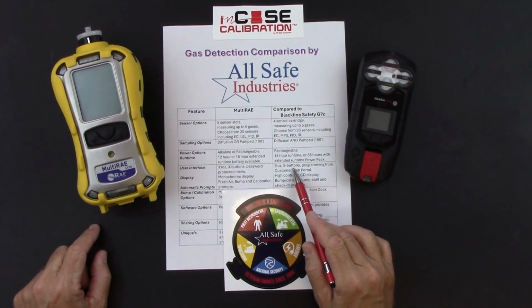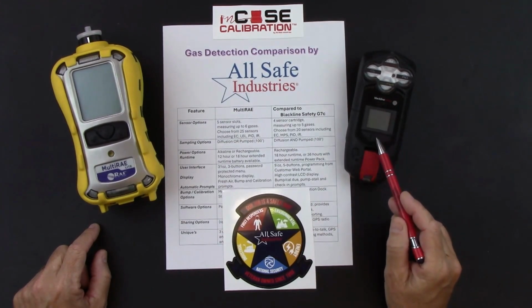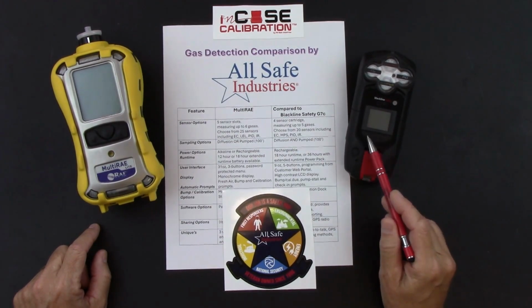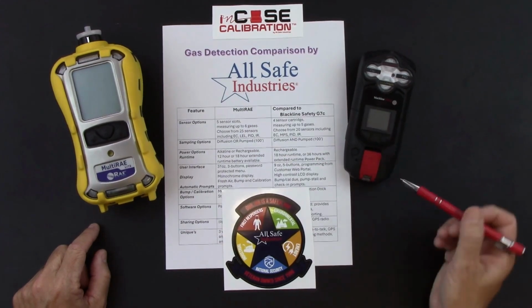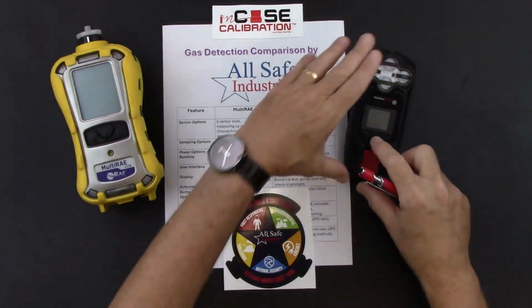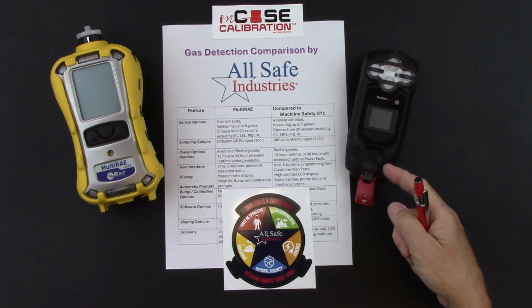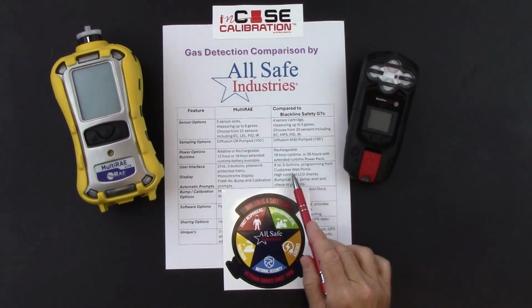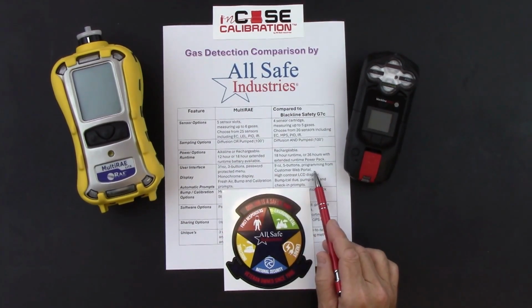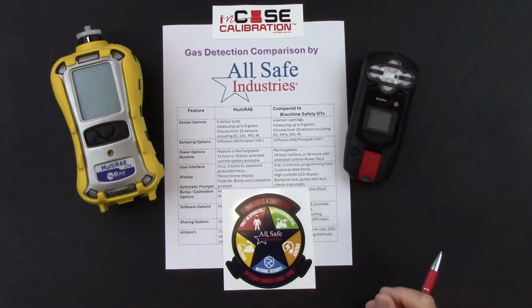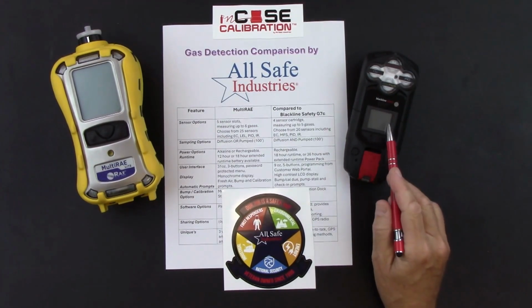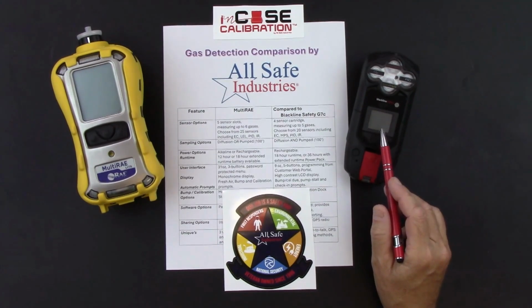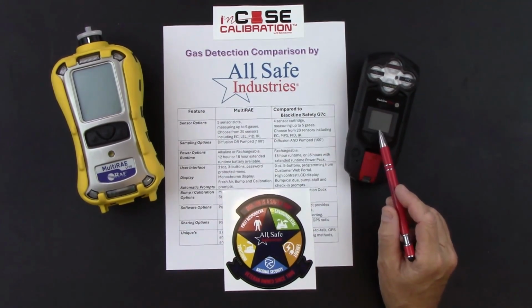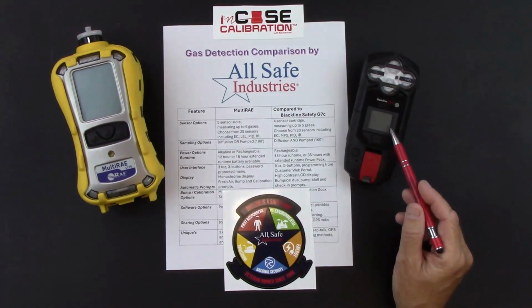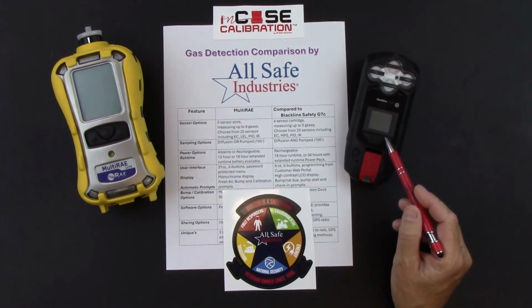It has 5 buttons to operate. It has a power button, it has an OK button, an up button, and a down button to navigate your on-screen menus. And then it has the SOS latch. So when you pull this, it is like pulling a fire alarm. It sends a signal to the Blackline Safety monitoring service. Programming is done through the customer web portal. So you would log into your portal to change your configuration settings on your G7c. It has a high contrast LCD display. You'll see that when it's in diffusion mode, it's a dark background with white characters. And when it's in pump mode, it's a white background with dark characters on screen.